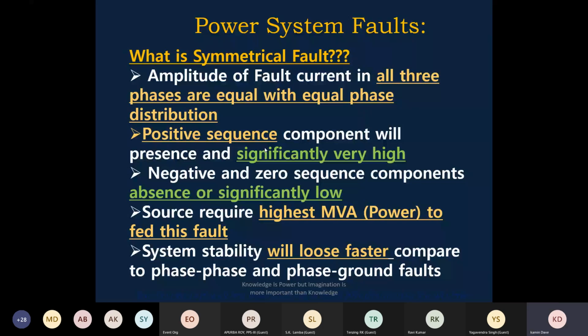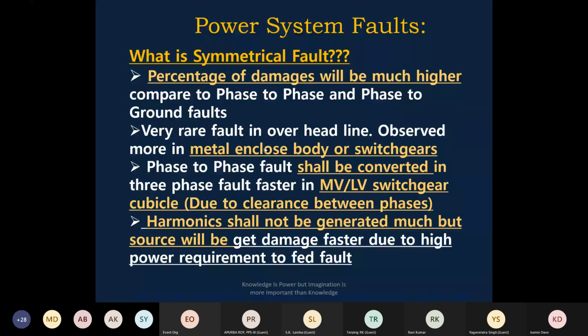And that is why the system stability will be lost faster compared to a phase-to-phase and phase-to-ground fault. That is why we can say the three-phase fault is a severe fault. The percentage of damage will be very high, even on the generator side as well as on the fault side, both sides, because the energy is very high. Energy is high, so damage will be very high.